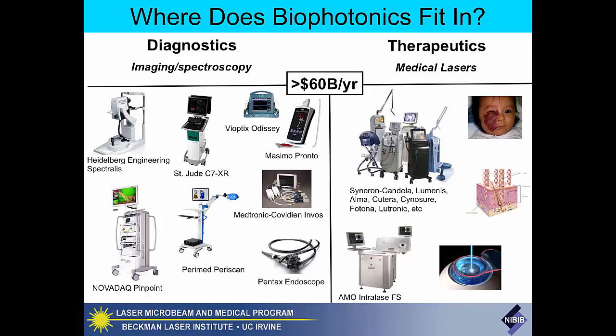One is tissue oximetry, primarily using near-infrared technologies. Devices from Vioptix, Masimo, Medtronic, Covidien are all tissue oximeters. These are all contact-based probes, and they work in the near-infrared and measure oxy and deoxyhemoglobin. But the output is a clinical endpoint called tissue oxygenation, which is a relative measure of oxyhemoglobin divided by total. You can measure that in tissue, or you can measure that just on the arterial side, and if you do that, then it's called a pulse oximeter.